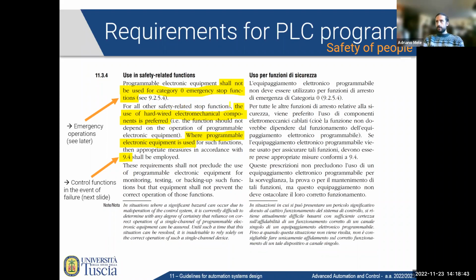All the other safety related stop functions, again, the use of hardwired electromechanical components is preferred. So even for non-safety critical functions, wired logic is to prefer. But where programmable controllers are used, then you should take some precautions, and we will see them in the next slide. There is a specific paragraph that discusses them. Of course, it tells you also that the requirements shall not preclude the use of programmable electronic for monitoring, testing, backing up such functions, and so on and so forth. But the equipment shall not prevent the correct operation for those functions.